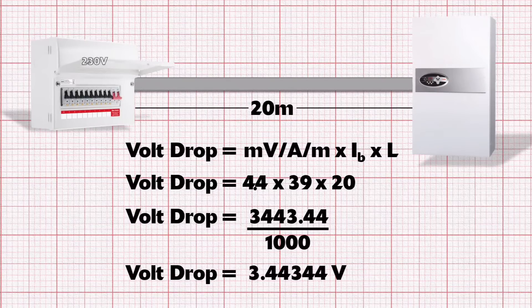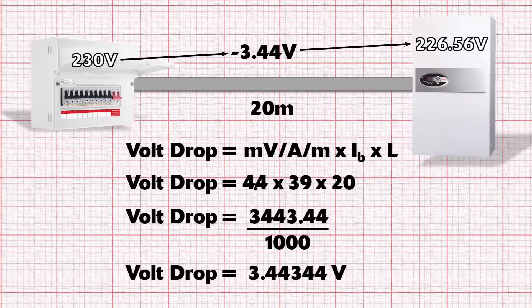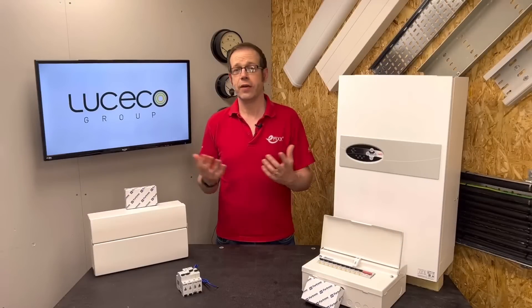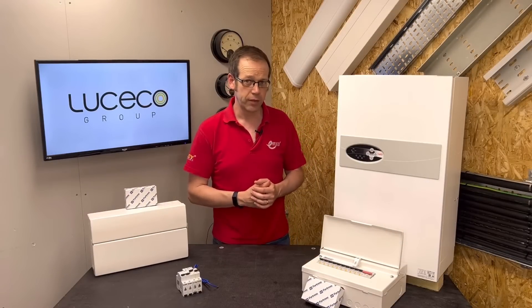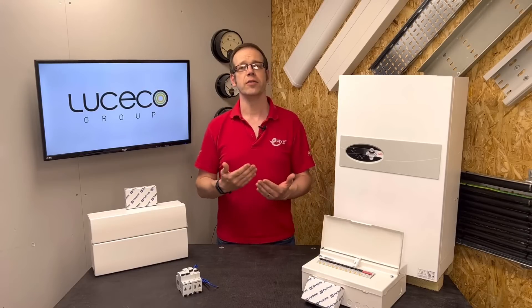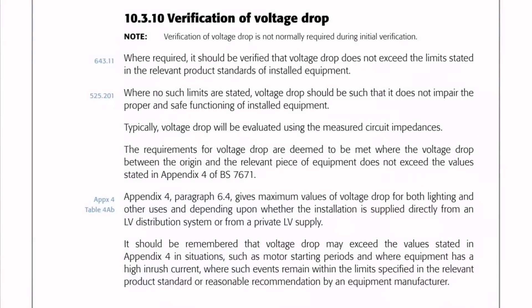So if the voltage at the consumer unit was 230 volts, the voltage at the boiler terminals would be 230 minus 3.44, giving us 226.56 volts. Is this value okay, or will our customer be taking cold showers? There are two ways to figure out if it's acceptable. The first is to use guidance from the IET. Under heading 10.3.10 of the on-site guide, we find information on verifying volt drop. It directs us that the requirements for voltage drop are deemed to be met where the voltage drop between the origin and the relevant piece of equipment does not exceed the value stated in Appendix 4 of BS7671. Appendix 4, paragraph 6.4 gives maximum values of voltage drop for both lighting and other uses, depending on whether the installation is supplied directly from an LV distribution system or from a private LV supply.